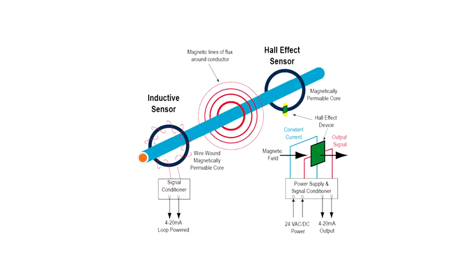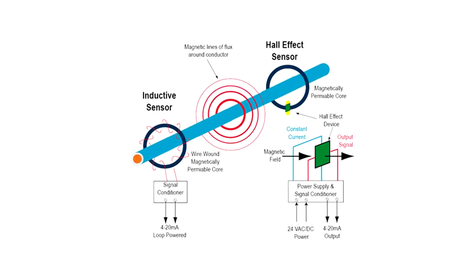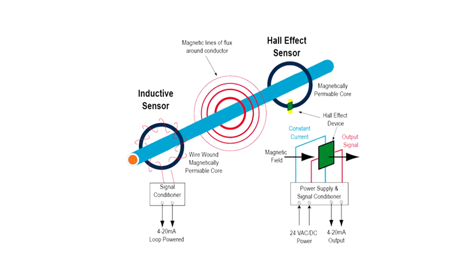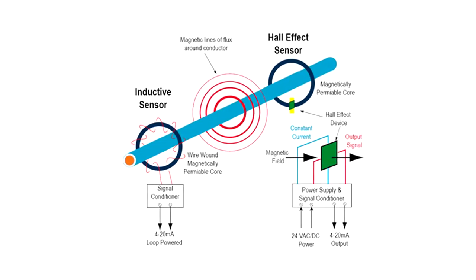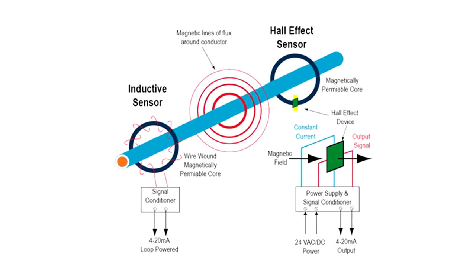Measuring direct current is impossible using the current transformer principle because the magnetic field from the wire is constant, so there's no magnetic flux. Therefore, no current is induced in the secondary winding.